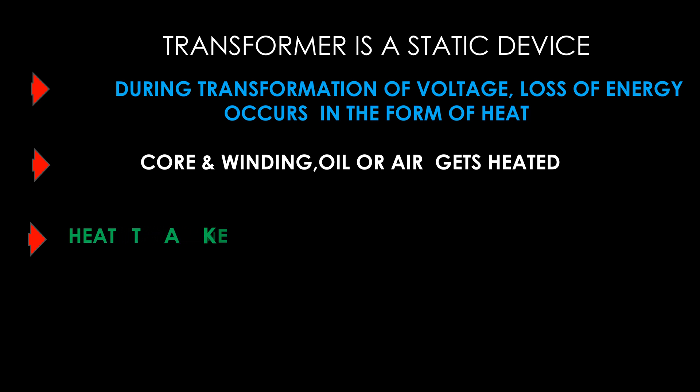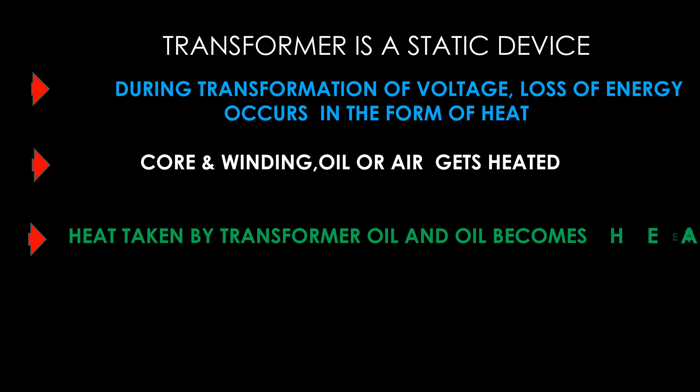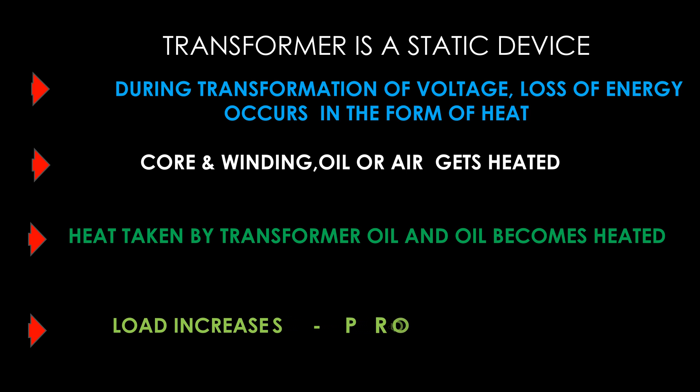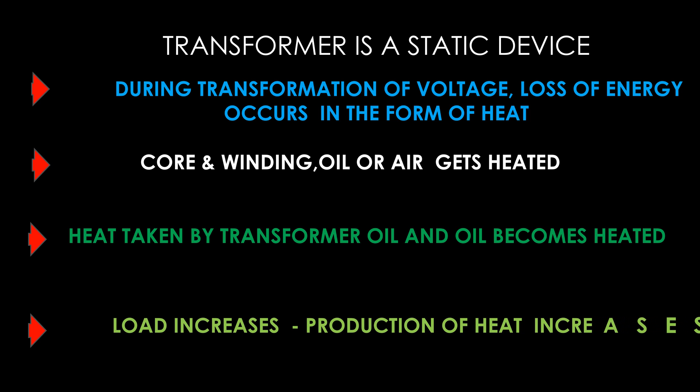A transformer needs cooling when load increases due to loss of energy in the form of heat. During conversion of voltage and thereby feeding of load, the core and winding become heated. This heat is taken by the transformer insulating oil, thus increasing the temperature of the oil. So transformer oil needs to reduce its excessive temperature through cooling apparatus, to maintain a suitable temperature and prevent any damage to insulation.